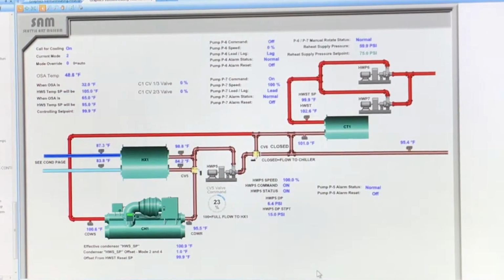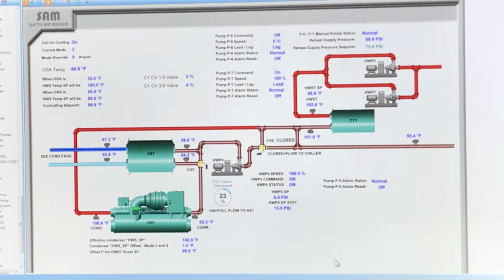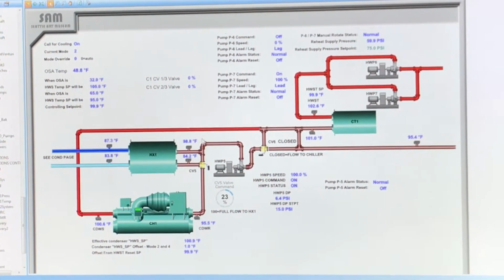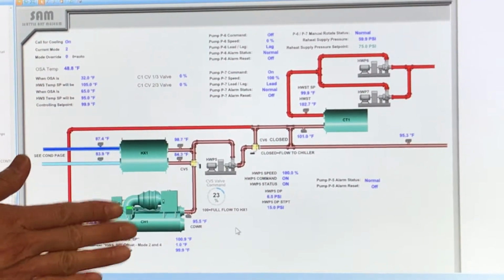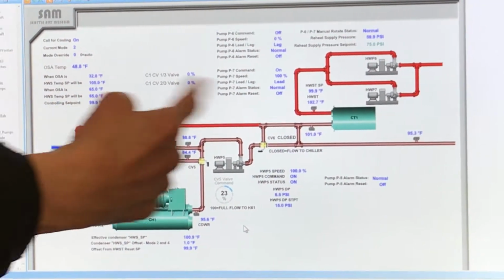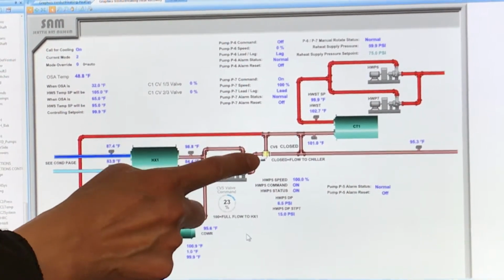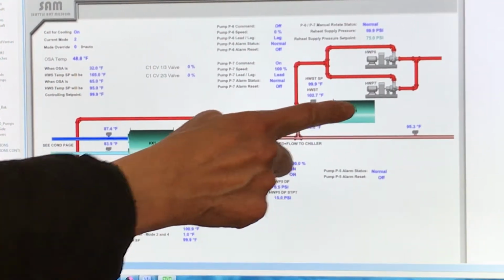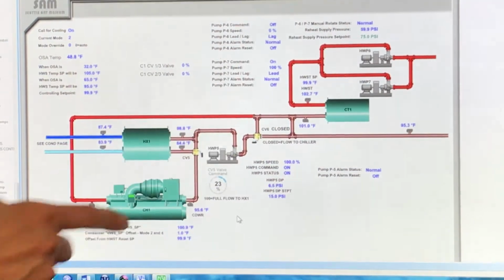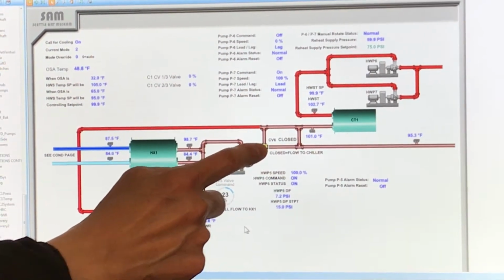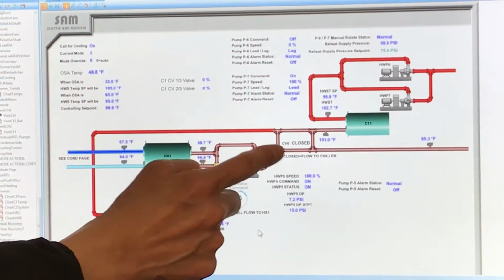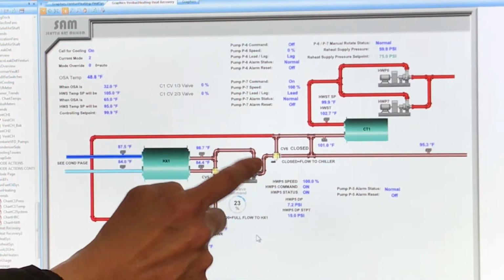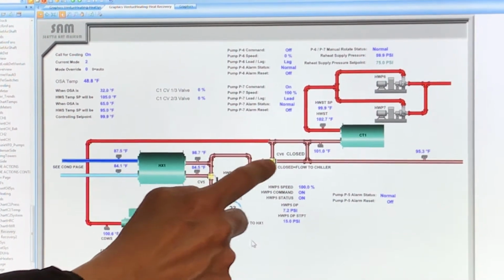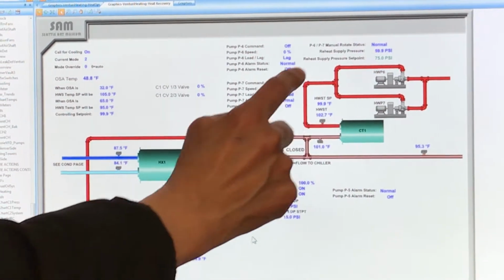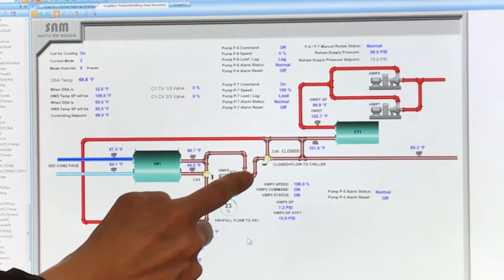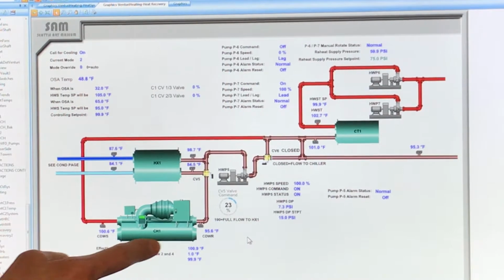Can I jump in? Sure. You want it back to the condenser page? No, this page. So basically, the system is like that. When this guy is running and you are delivering condenser water to the heating water loop, this valve will actually be closed. Okay. And what valve is that? Oh no, this one will open and you are actually sending water through here and through here or through here.